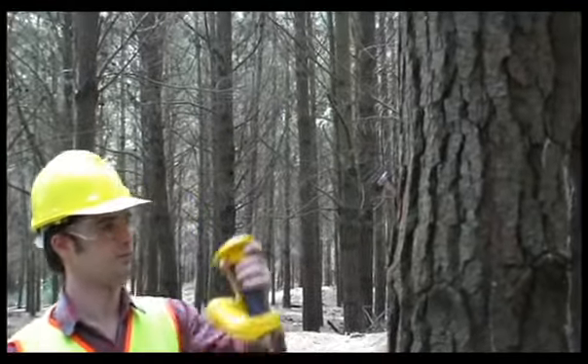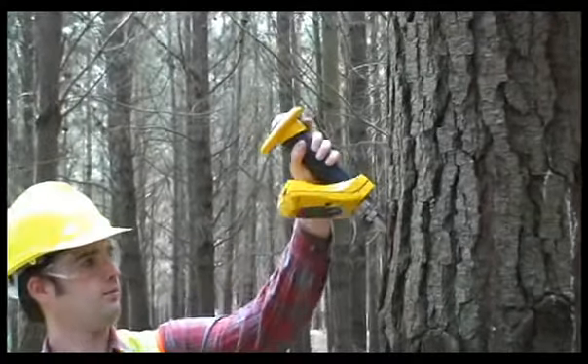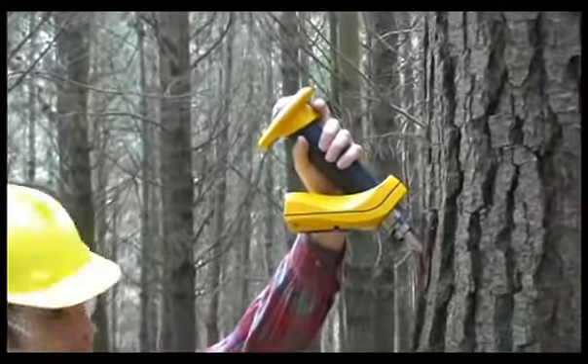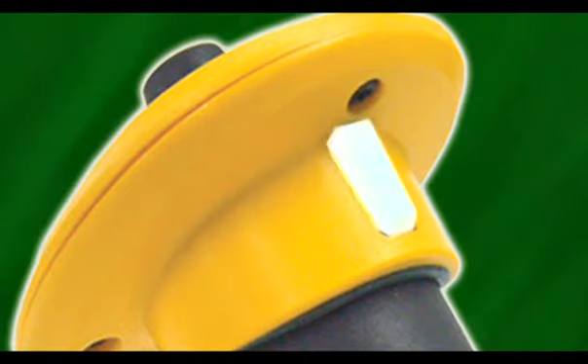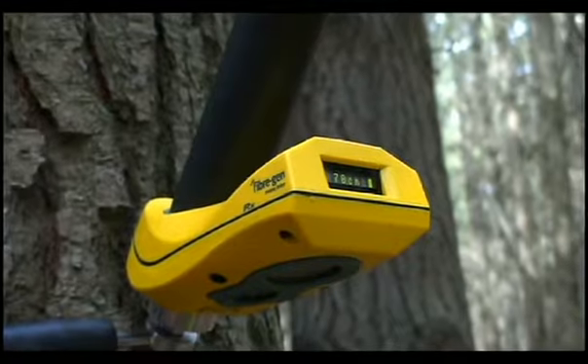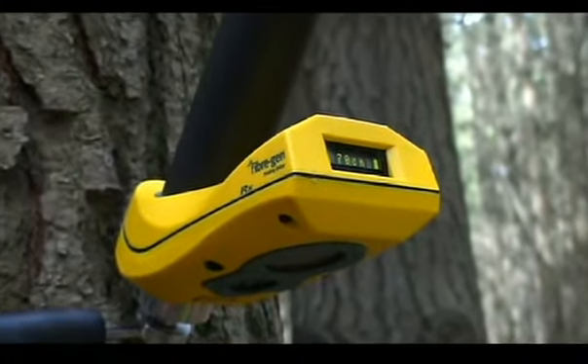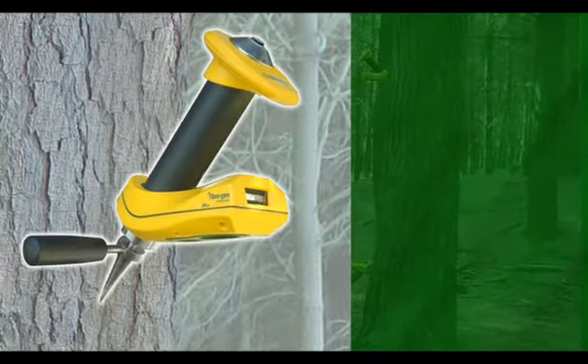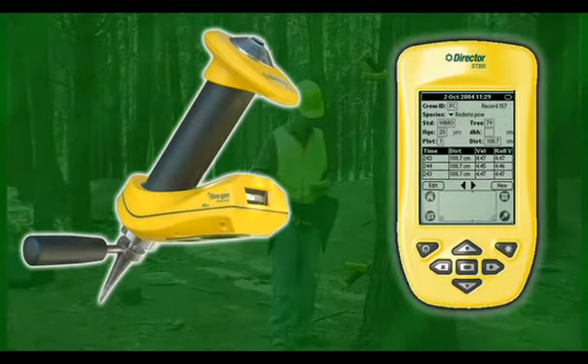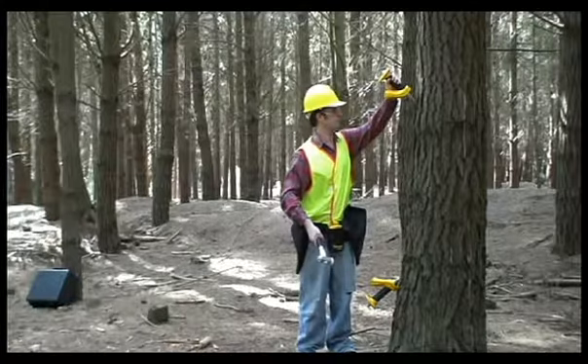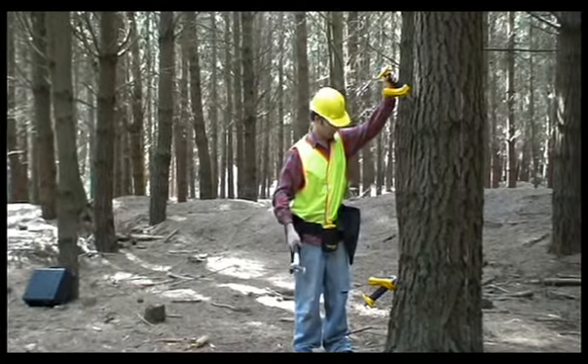Remove the RX probe from the holster and insert the probe into the spike. Switch on the RX probe by momentarily pressing and releasing the trigger. You will see the serial number and battery icon appear on the screen. Within a few seconds, Bluetooth communication will be automatically established between the RX probe and the PDA. This will be accompanied by a short beeping sound and appearance of the Bluetooth icon on the upper right-hand side of the PDA screen. Depress the trigger again to activate the laser.